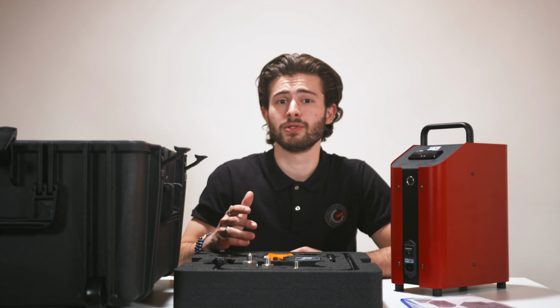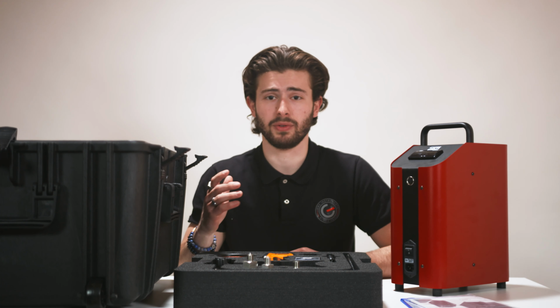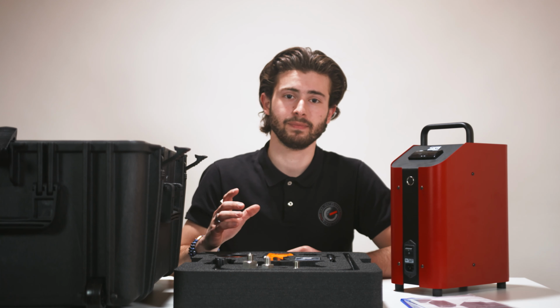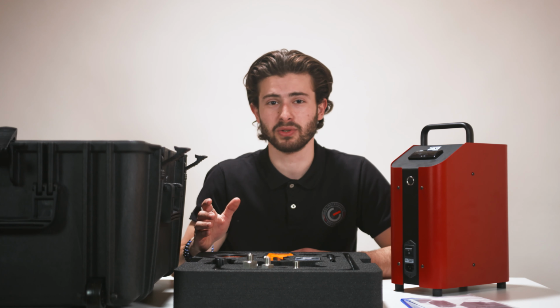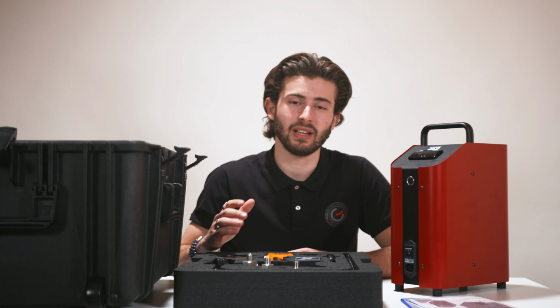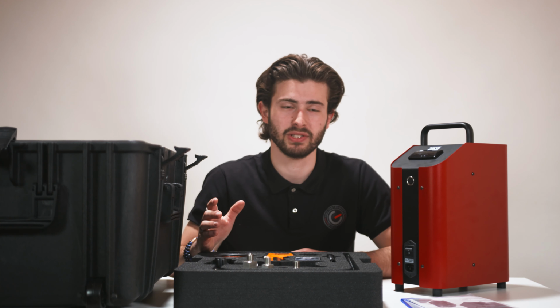And the percentage difference can then be compared to the measurement accuracy of the instrument, which is also in percentages most of the time, and then see if it's still maintained. If not, the instrument should be sent to a calibration facility.